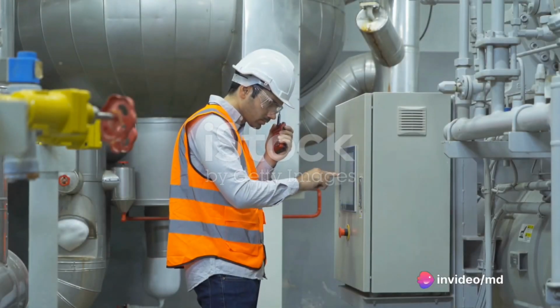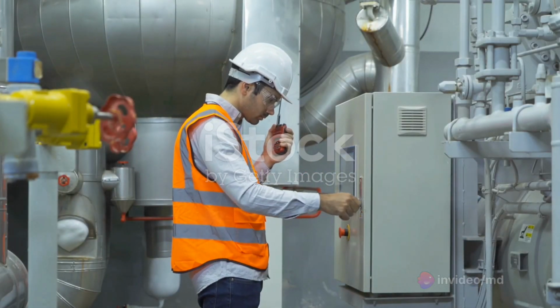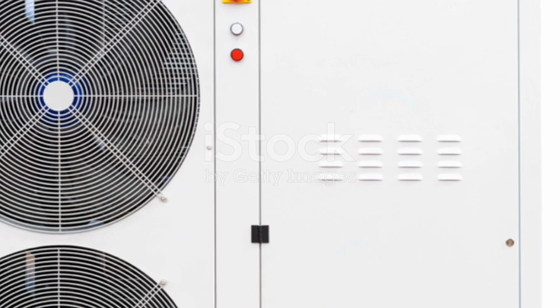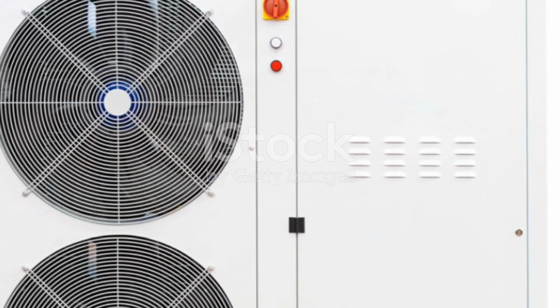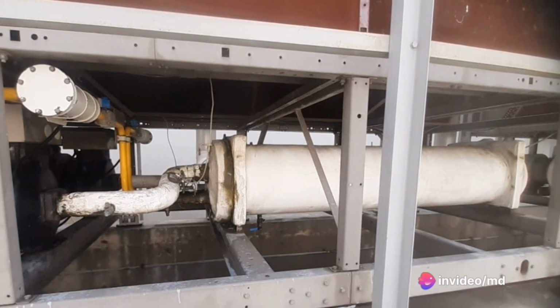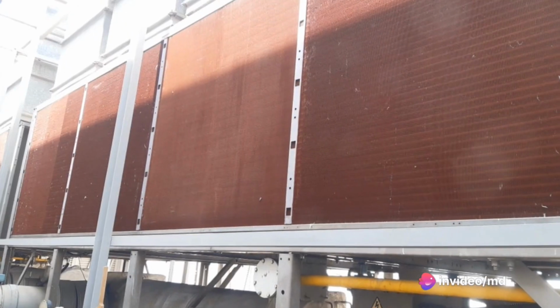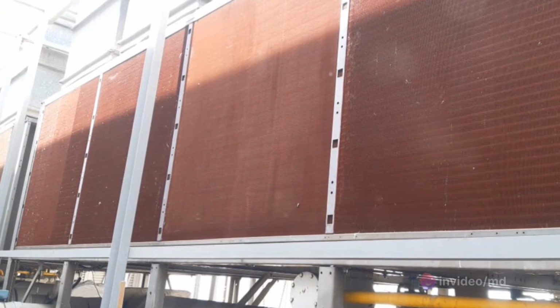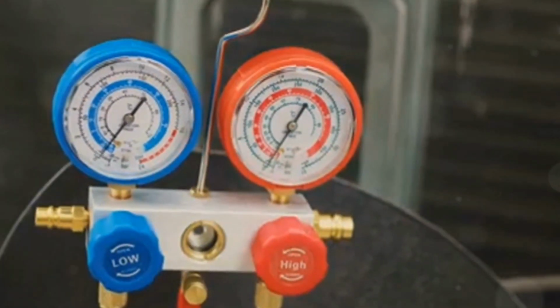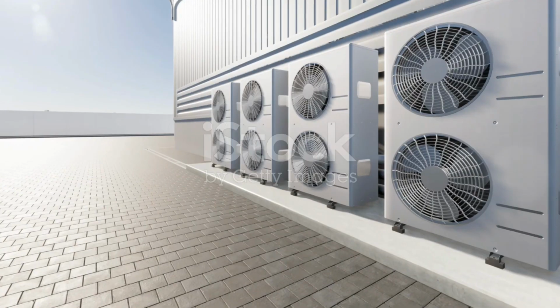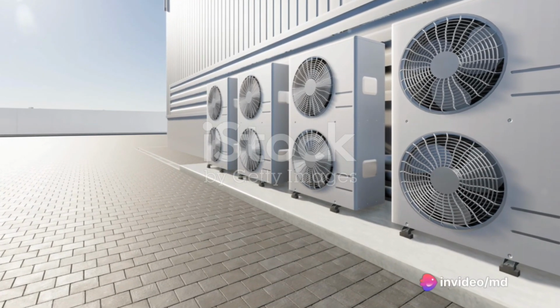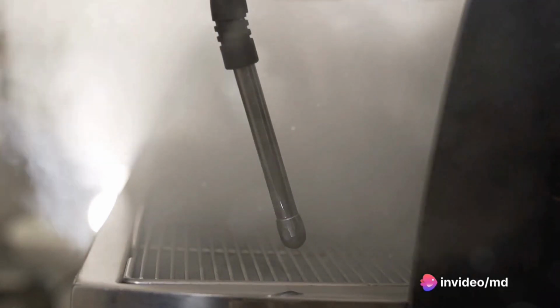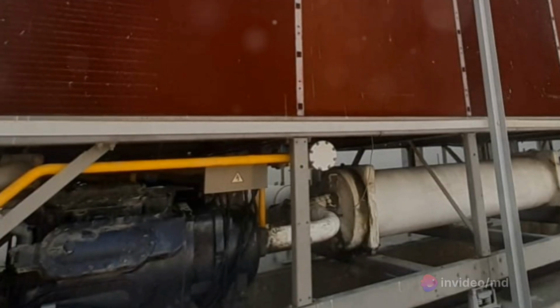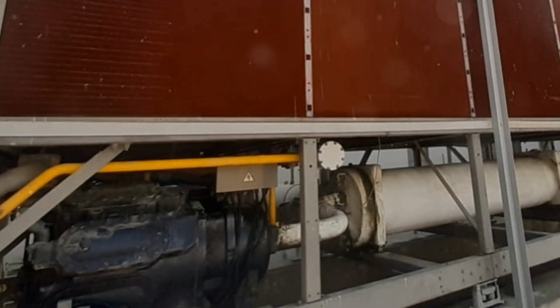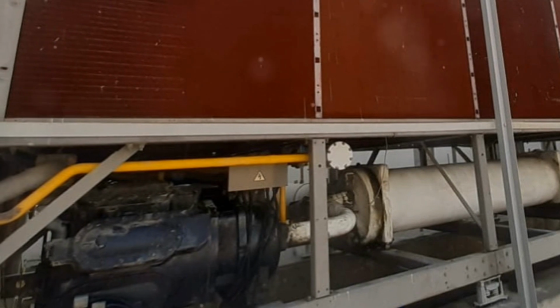Understanding how a chiller works might seem complicated, but it's really not. A chiller works on the principle of the vapor compression cycle or the vapor absorption cycle. Let's break it down. In a vapor compression cycle, the refrigerant circulates between an evaporator and a condenser. The process starts with the evaporator, which has a low-pressure, low-temperature refrigerant. Here, the heat from the process water or air is absorbed into the refrigerant, which causes the refrigerant to boil and evaporate. This refrigerant vapor then goes into the compressor, where it gets compressed to a high-pressure, high-temperature gas.